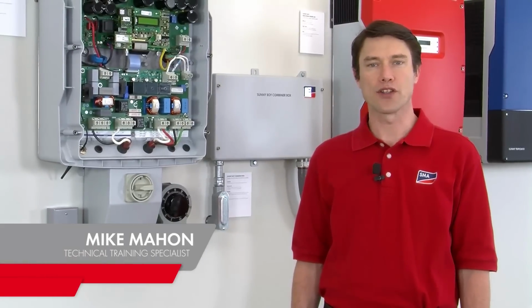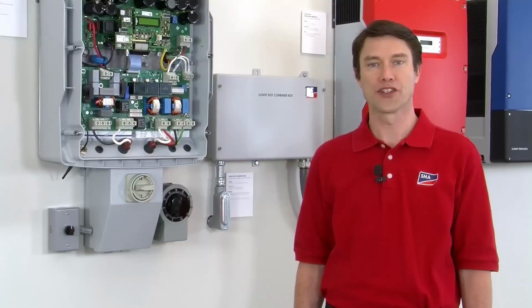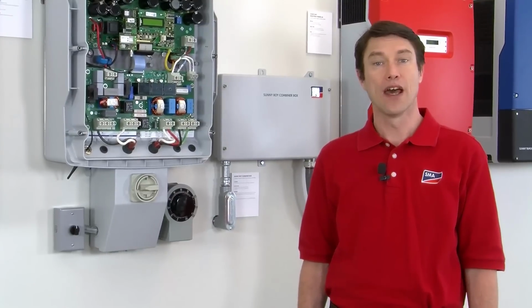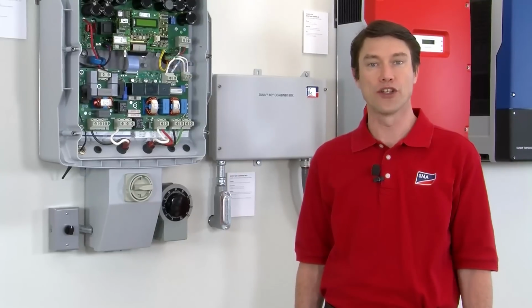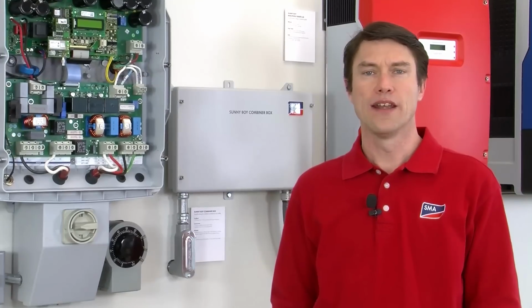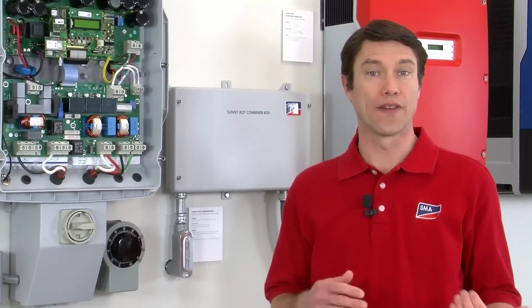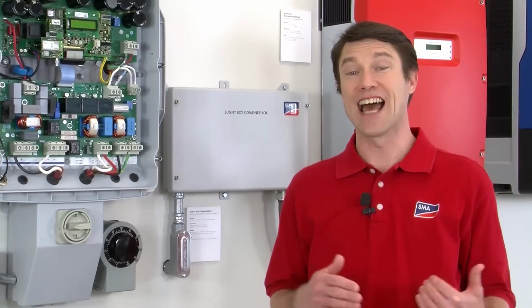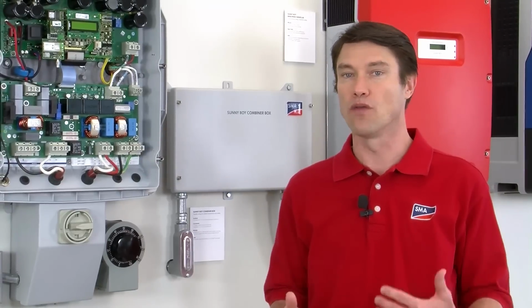In today's segment, we're going to talk about a common error code with our Sunny Boy series of string inverters. And that error code is VAC, or voltage on the AC side. Now, this error code arises if the voltage on the AC side of the inverter is out of spec.